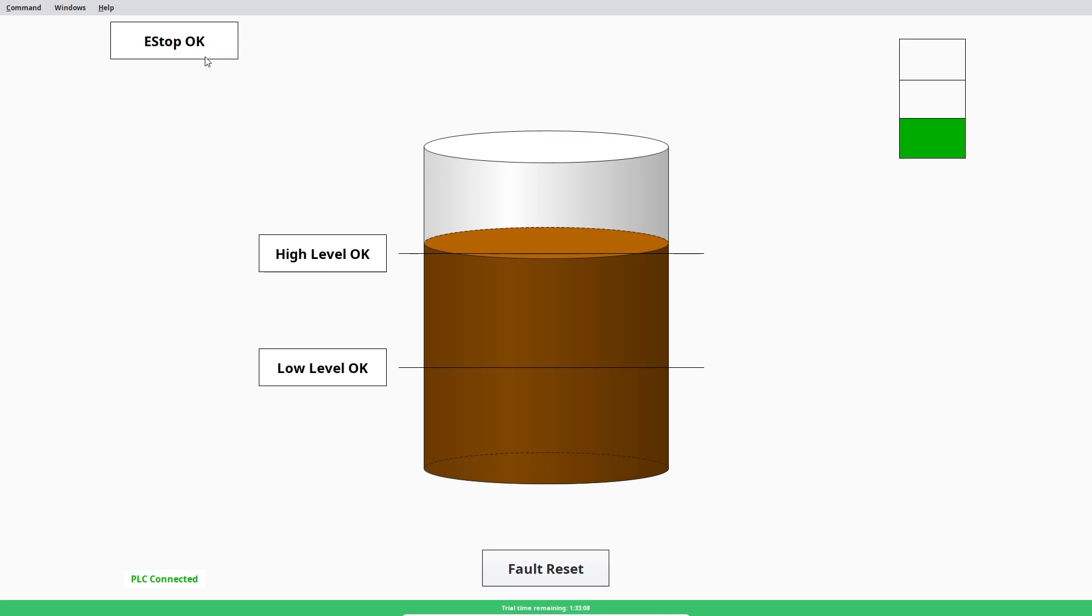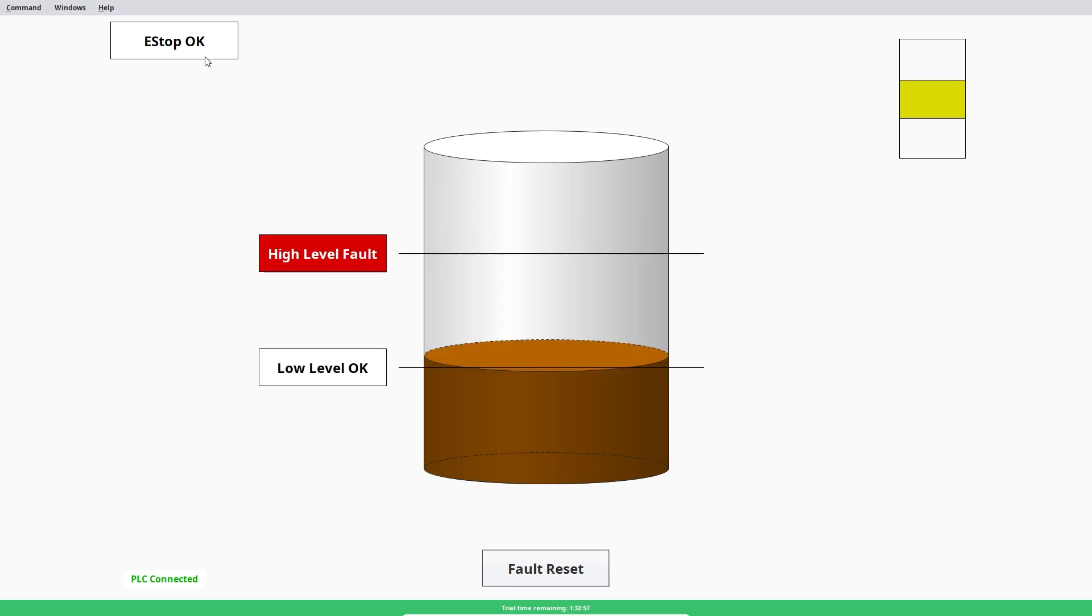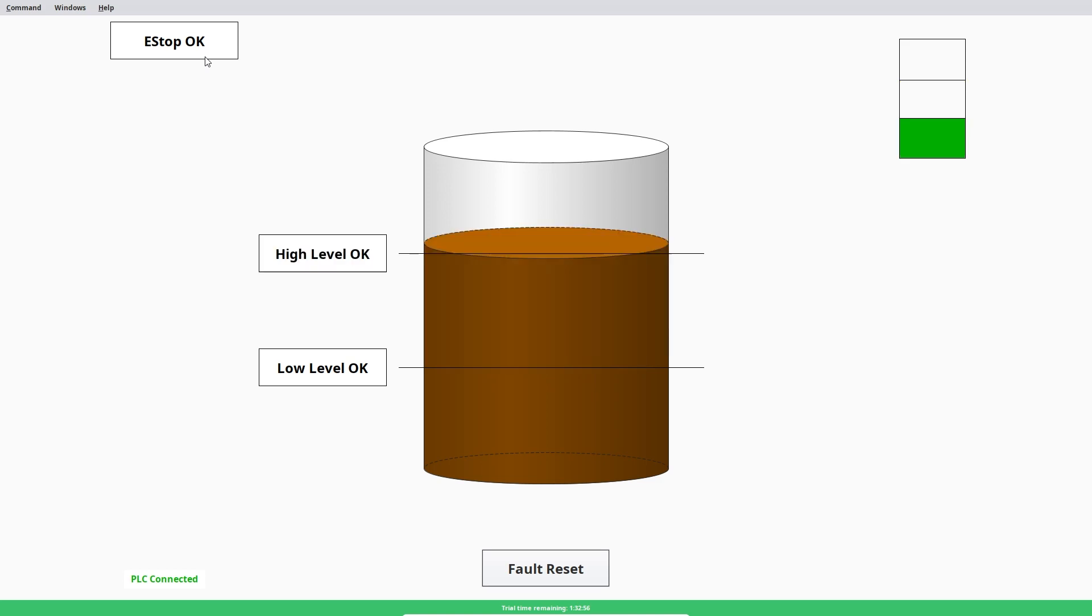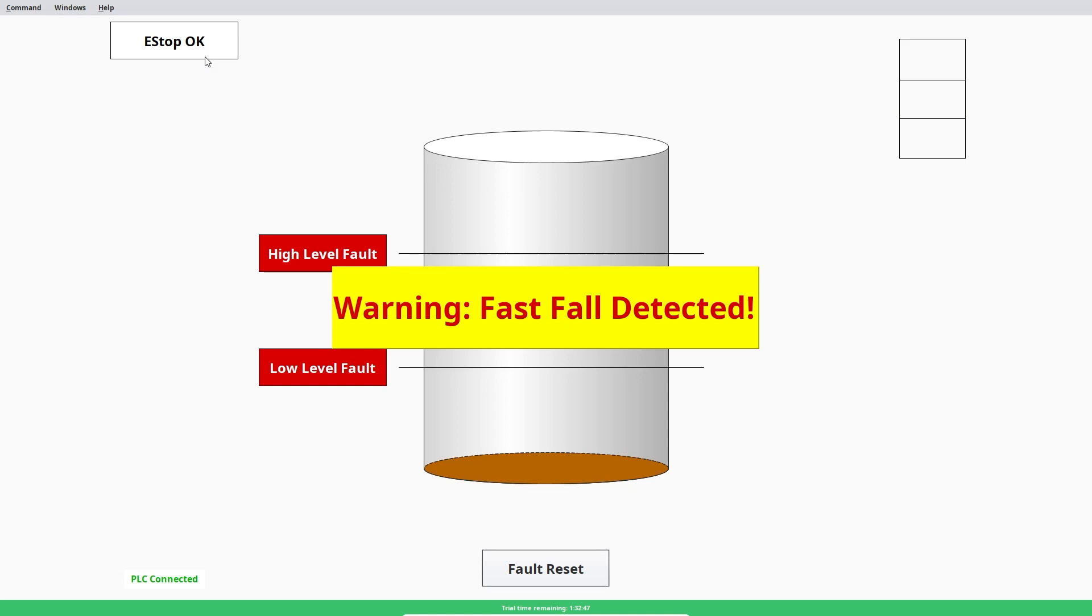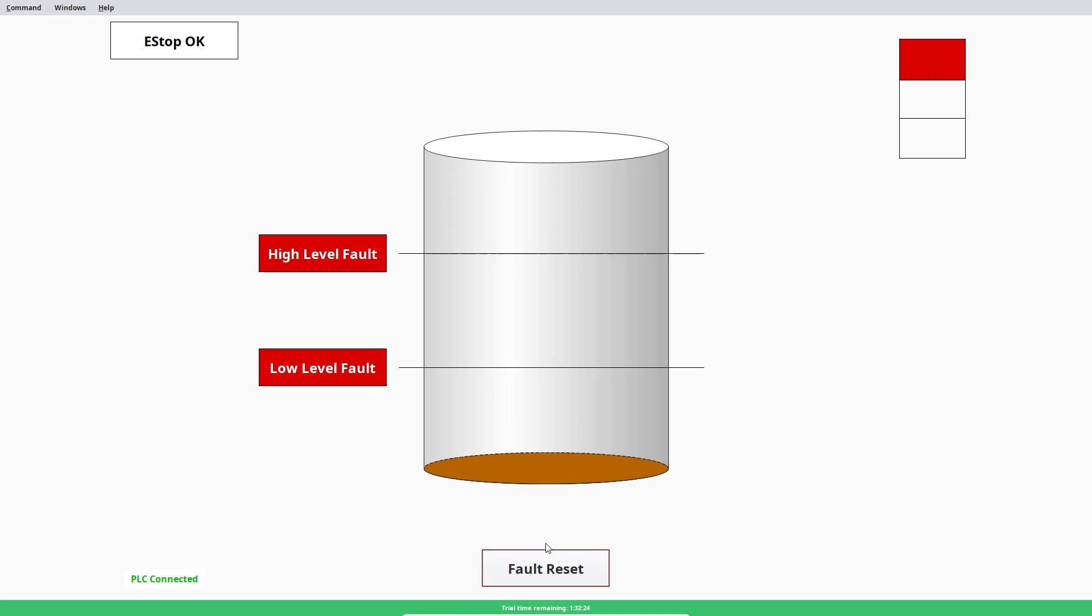And then the main purpose of the program was to detect a fast fall. So that means to say that you've had your tank full and then you lose your high level sensor. And then if you lose your low level one too quickly, it will then trigger a fast fall detected. And so it's a really simple HMI. And I've also got it so that the HMI isn't just reading data from the PLC, but it can also write to the PLC by if I click this fault reset button, it will then clear that fault.